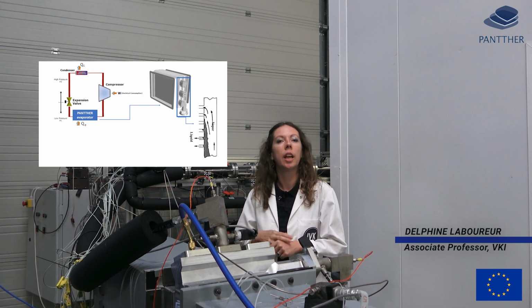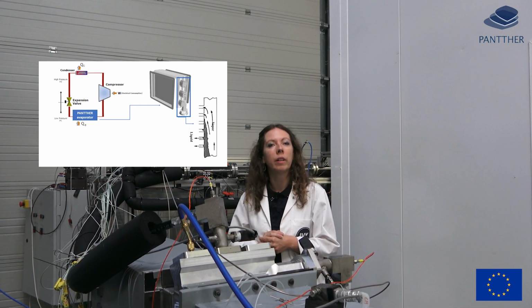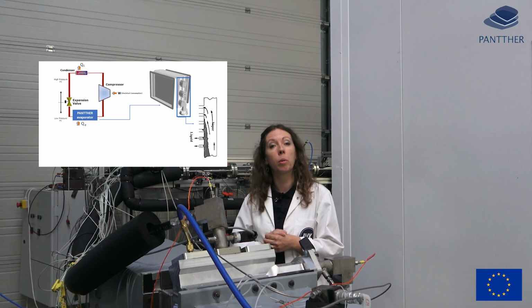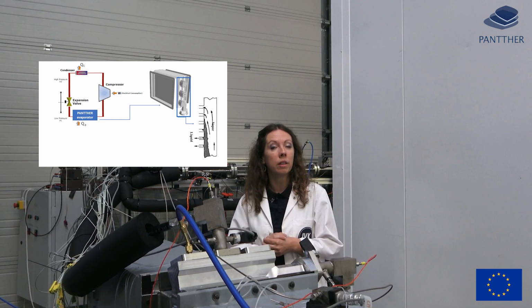Vapor cycle systems are loop systems that are used for equipment cooling and air conditioning. These are composed of 4 main equipments: a compressor, a condenser, an expansion valve, and the evaporator. And most of the cooling is coming from the evaporator, where the heat transfer is provided by a phase change of the fluid, which is most of the time a refrigerant. In order to improve the efficiency of such equipment, one of the key issues that remains today is the flow maldistribution that can account for up to 30% of losses.